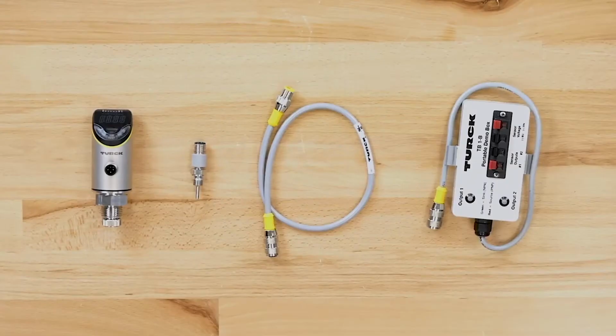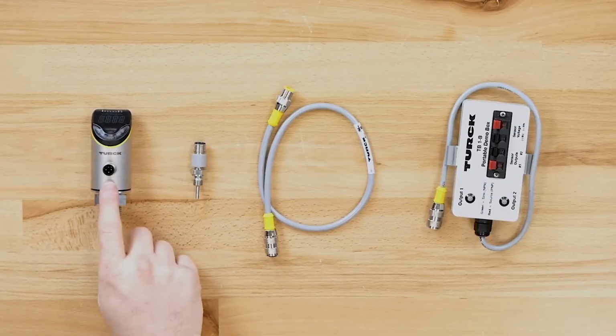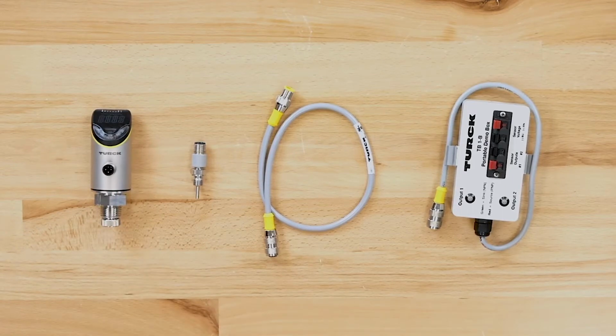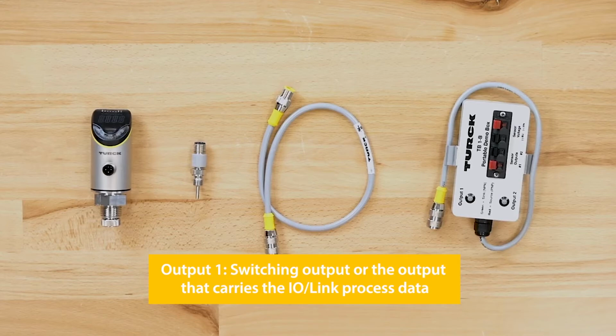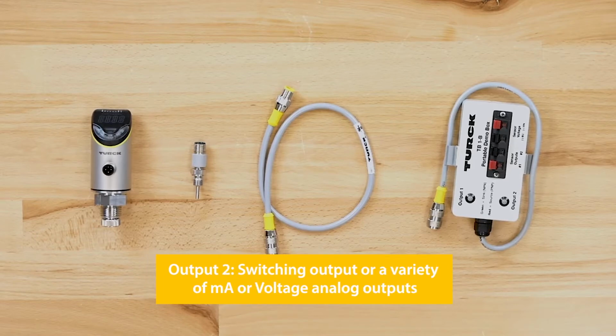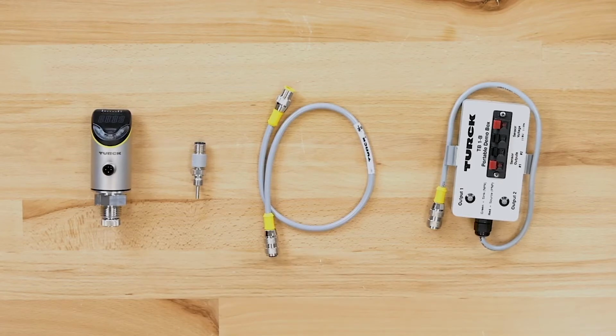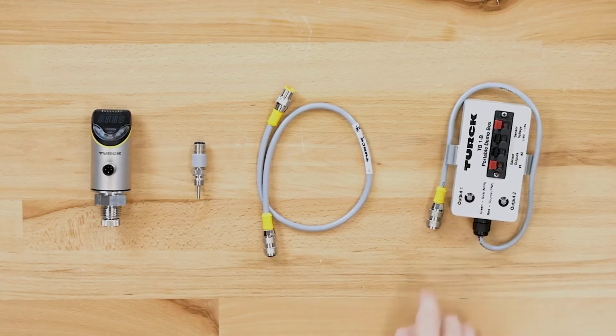For this tutorial, we are going to be using a TS720 TS Plus sensor. This sensor has two outputs. Output 1 can either be used as a switching output or the output that carries the IO-Link process data, but not both at the same time. Output 2 can be configured to be a switching output or a variety of milliamp or voltage analog outputs. We will also be using a temperature probe, a 4-pin M12 extension cordset, and a Turck sensor test box.